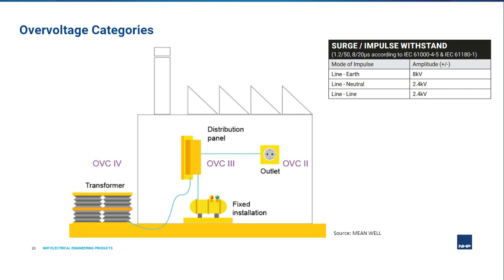There are four main overvoltage categories which have been defined and I will reference it to the diagram that you see on the slide. Cat 4 is the highest overvoltage category, which means that components and equipment are likely to experience high energy voltage transients at this point, especially in comparison to other equipment located in other overvoltage categories, as in comparison to Cat 4, which is installed directly at the utility side. The example on the diagram shows a utility grade transformer for which Cat 4 ratings apply. Other examples include service entrance boards, which includes components such as your surge protection devices, utility metering, isolators, and liveline indication devices, such as the REMLIVE unit.